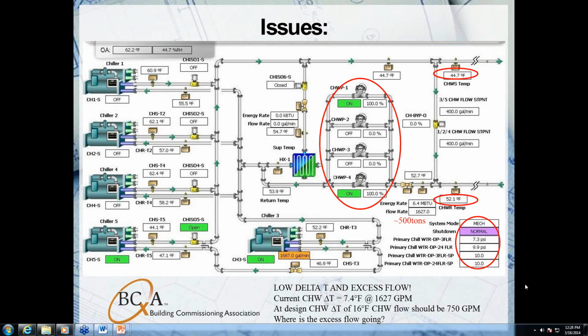And to chime in too, we've seen this building get handled basically by one chiller. And Mark, you can correct me, I think even up to about a 90-degree day, they only need one chiller. So their peak load is about 800 tons. And they spend a lot of hours below 70, probably 65 degrees. They only need one of the 400-ton machines.